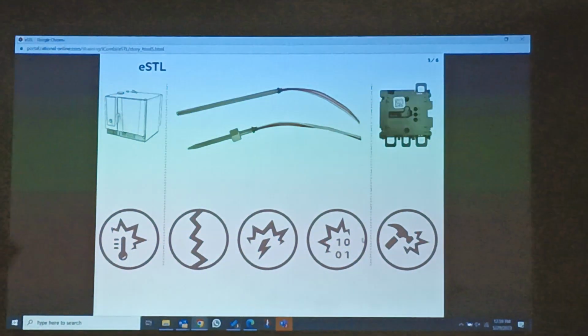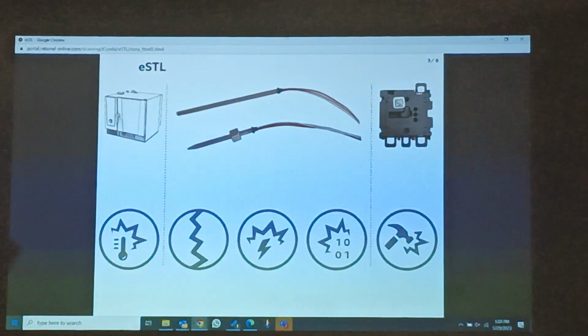Okay, so we have four things that can happen in the ESTL. The first one is sensor not connected. The second one is sensor short circuit. The third one is sensor out of logic area. And the fourth one is the sensor has a high temperature in the cabinet, and the fifth is the ESTL broken itself. So how can we identify which error code, what is the meaning of this?